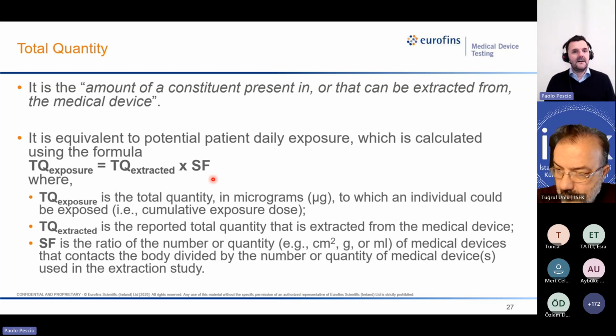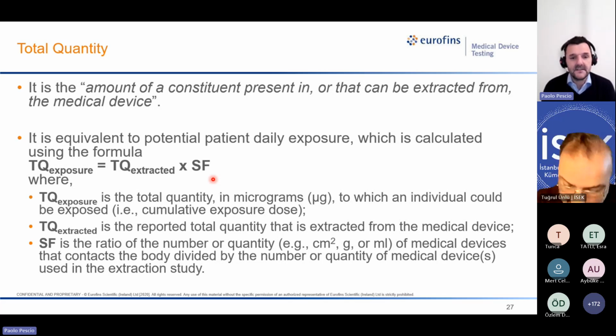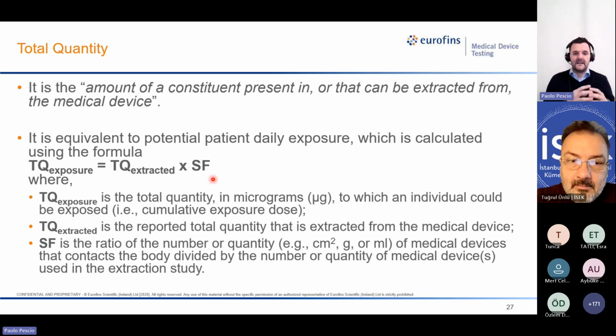Let's make another example just to add more clarity on this concept and why we are using the so-called SF value, to take into account the quantity of the medical device that contacts the body and the quantity or number of medical devices used in the extraction study. Let's do a different example. For any reason, you have performed an extractable study for a device of, let's say, 100 centimeters square, because otherwise it was not possible to test due to some limitation in the test system. Probably even because at that time only that specific size was available for test. That's fine.